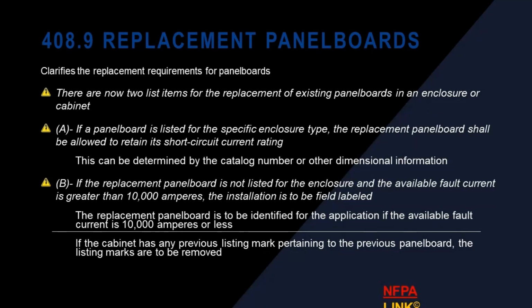Okay, replacement panel boards. There are now 2 list items for the replacements of existing panel boards in an enclosure or cabinet. A, if a panel board is listed for the specific enclosure type, the replacement panel board shall be allowed to retain its short circuit current rating. This can be determined by the catalog number and other dimensional information. B, if the replacement panel board is not listed for the enclosure and the available fault current is greater than 10K, the installation is to be field labeled, meaning we need to get a nationally recognized testing lab out to take a look at it and see what's going on. The replacement panel board is to be identified for the application if the available fault current is 10,000 amps or less. If the cabinet has previous listed markings pertaining to the previous panel board, the listing markings are to be removed.